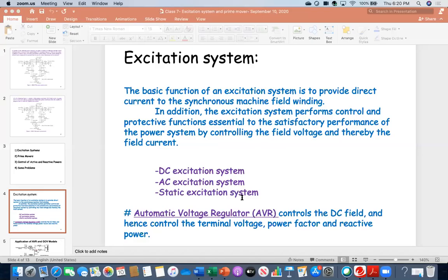So go back there. This is the three systems: DC excitation, AC excitation, and static excitation. Still all over the world, these three systems prevail. These days, to avoid these things—since it's complicated and you are dependent on some sources, and it incurs some cost—and in case the system does not work properly, it will not be magnetized and terminal voltage will be low.